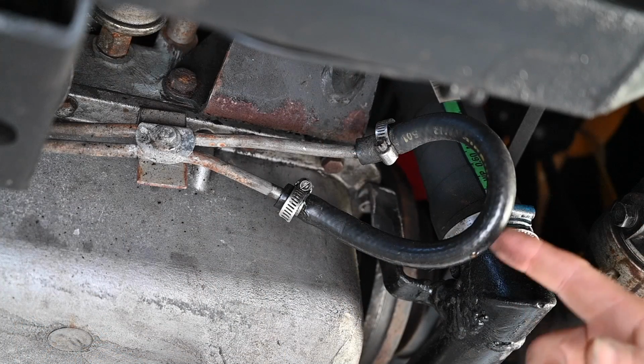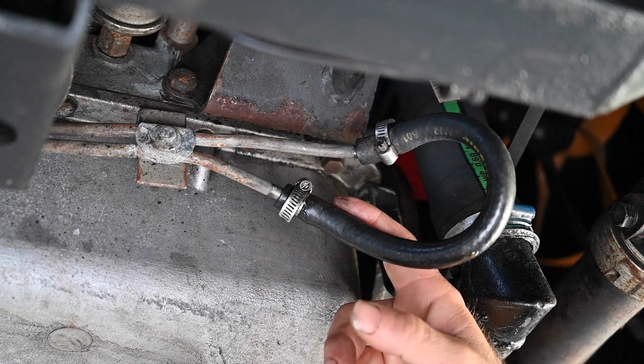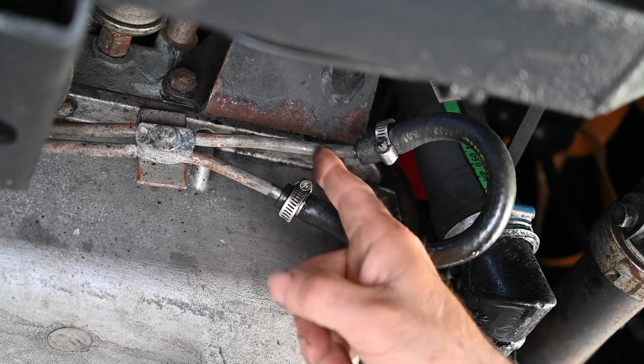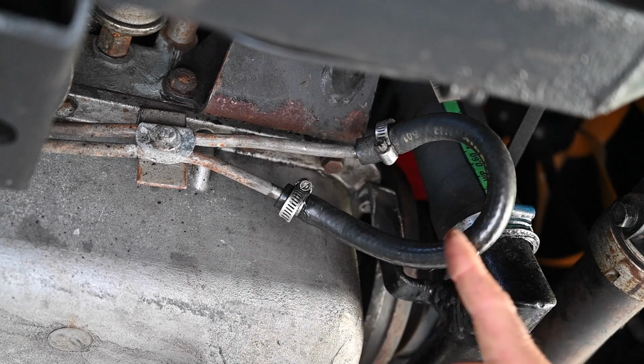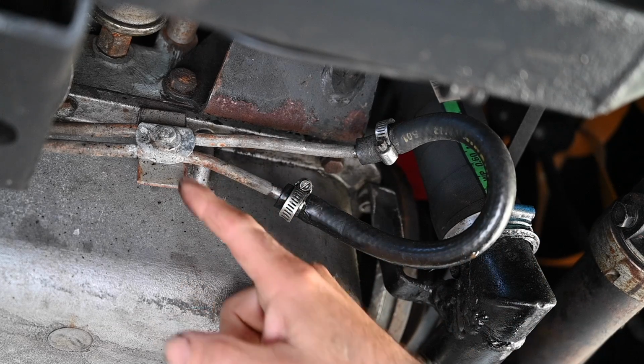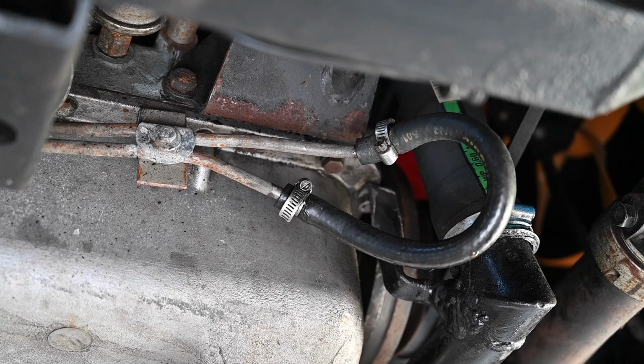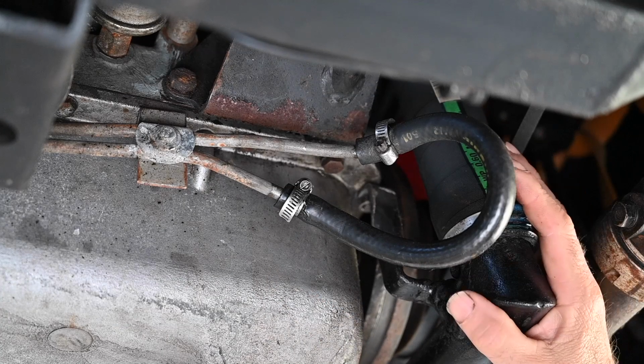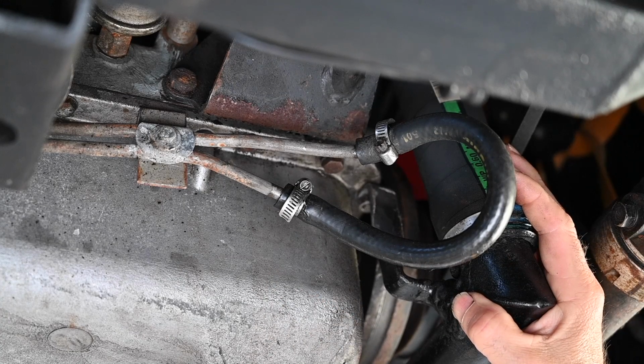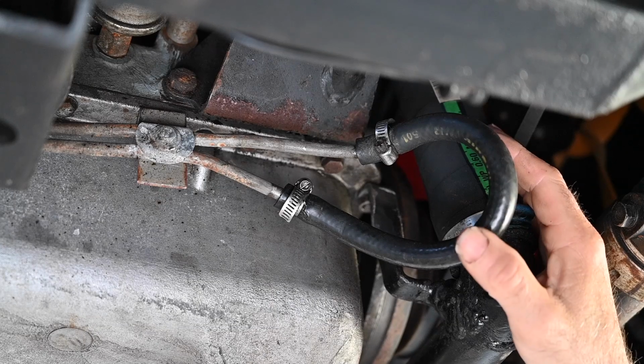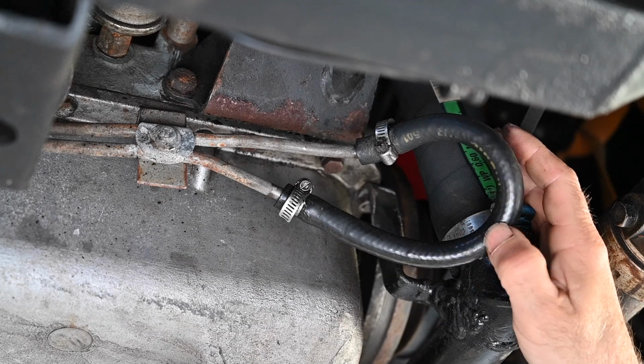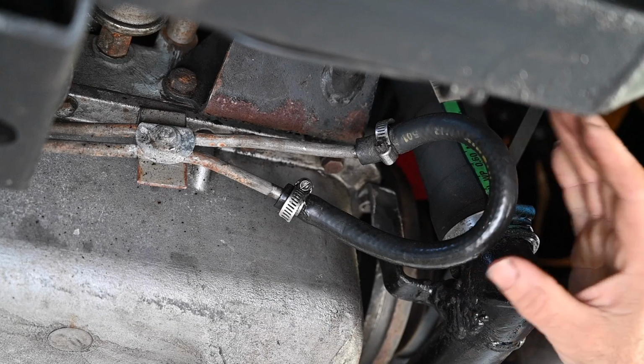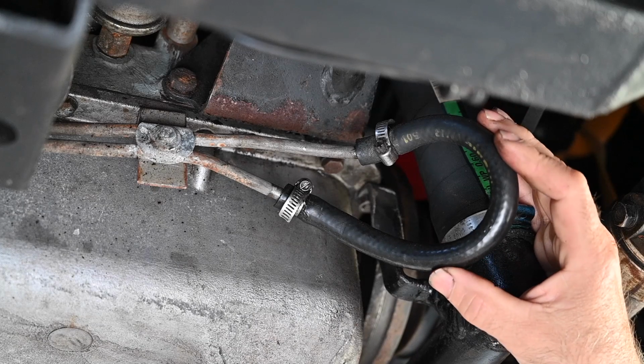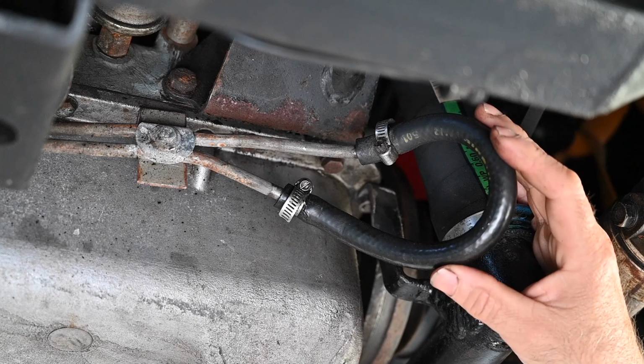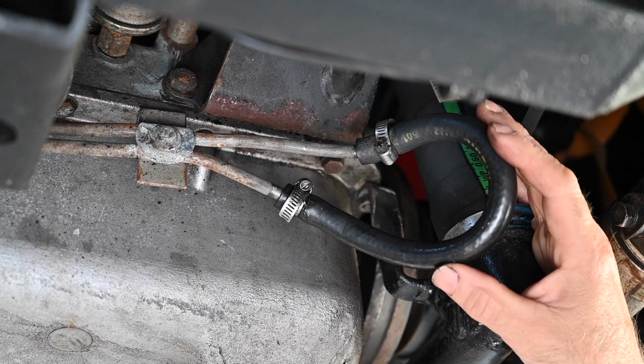Look what they've done - they connected a loop, taking the hot oil coming from the gearbox and looping it straight back in. So there isn't a lot of cooling going on. It's supposed to connect to the heat exchanger, but it isn't. Somebody in his own mind decided this was a good solution, and it's not. Most likely this is the real cause of the problem with the automatic transmission system.